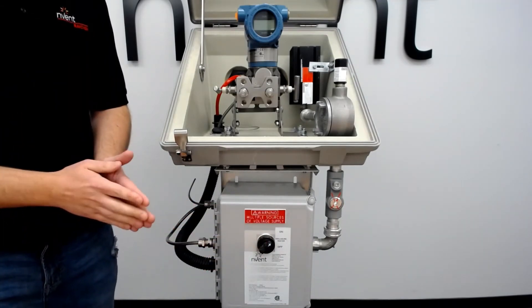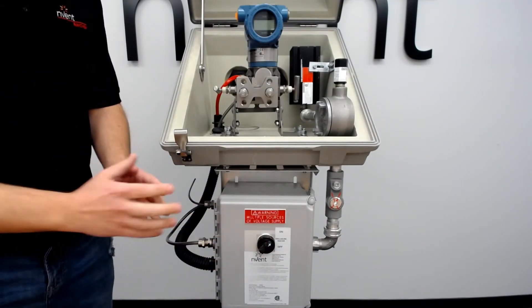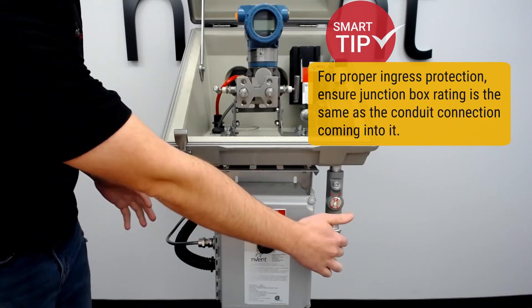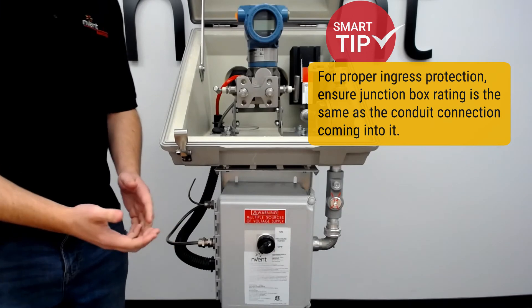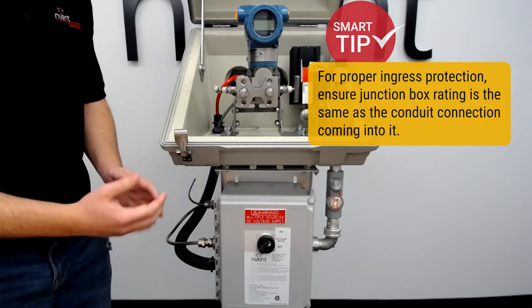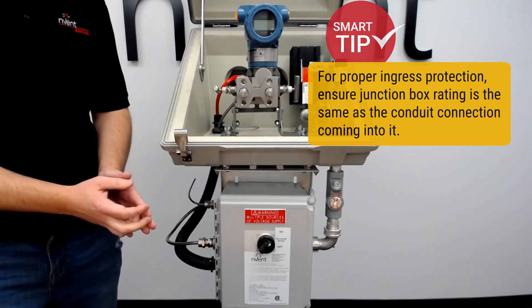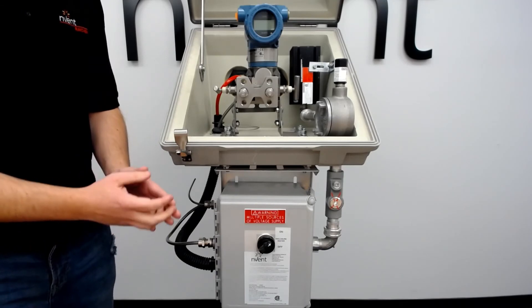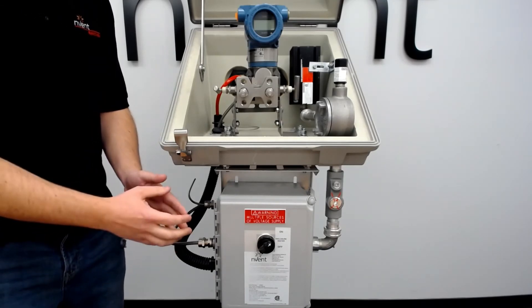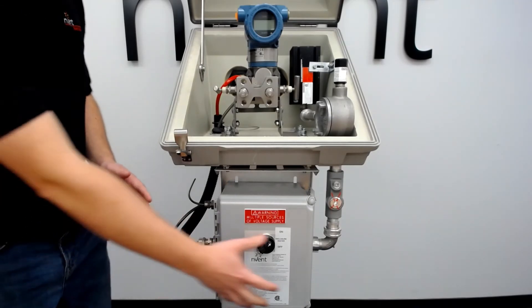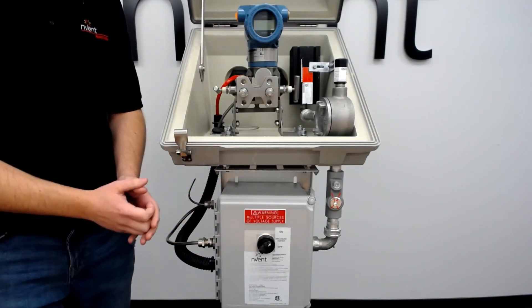We want to make sure that if you have a 4X rated junction box, you keep the penetrations into it rated to the same ingress protection rating. That's important to think about, especially when bringing cabling in - use 4X connections into the junction box, otherwise it loses its ingress protection rating and has the potential for water to get in.